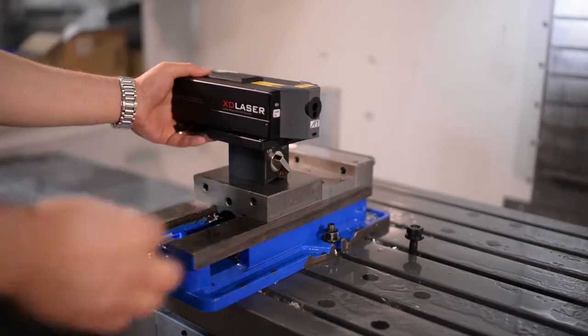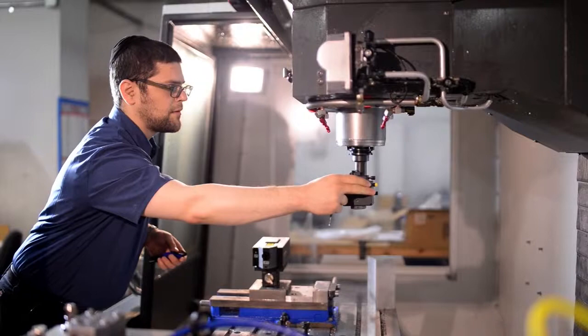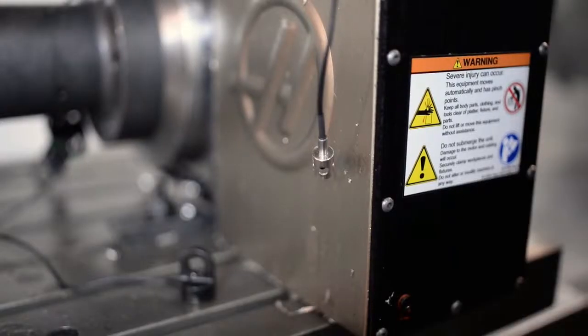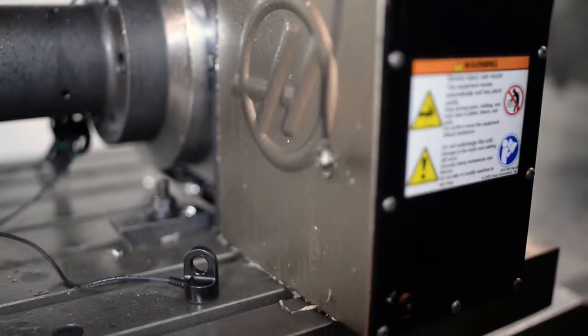Using the magnetic base, mount the XD on the bed of the machine. The sensor should be mounted into the spindle of the machine. Next, mount the weather sensor to account for environmental variance throughout the measurement.